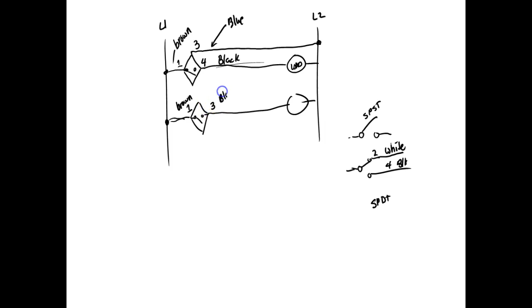This is going to be your inductive sensor, which is a solid state sensor. It's going to drop more voltage than a triac does, so we'll notice that this guy will drop on average around 4 volts, because not only is it running the contact, it's also running the sensing element inside there. It's running the oscillator, the sense circuit, and the flip-flop, running everything inside.